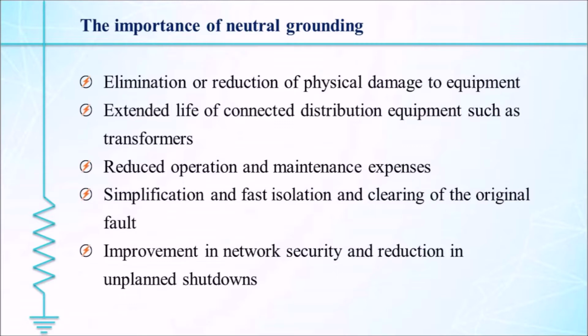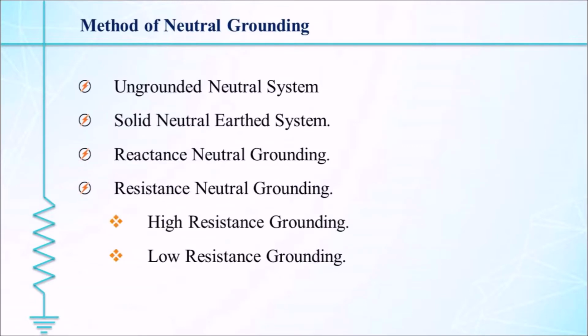Elimination or reduction of physical damage to the equipment, extended life of the connected distribution system such as transformers, relays, etc. Reduced operation and maintenance expenses, improved network security and reduction in unplanned shutdowns. Here we show the methods of neutral grounding. First is the ungrounded system, second is the solidly or directly grounded system, and then the reactance and resistance grounding systems. The resistance grounding system is again split into two parts, high resistance grounding and low resistance grounding.